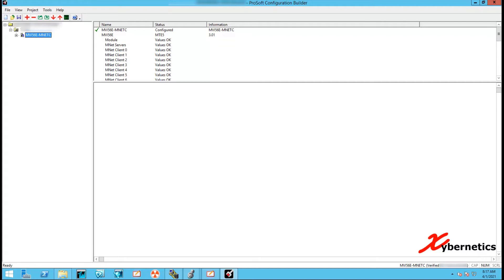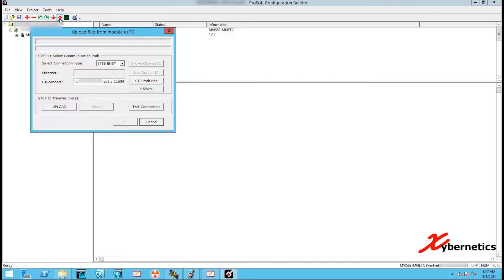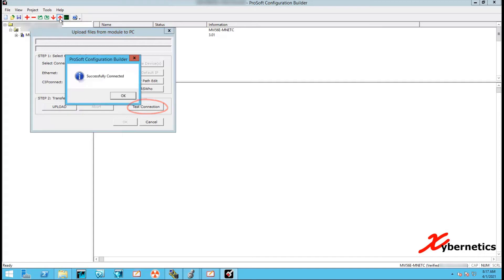The first thing I normally like to do is to read the configuration file from the ProSoft module itself. Click on the red arrow and a pop-up window will appear saying 'upload files from module to your PC.' The first four numbers on the CIP Connect is your IP address of your PLC, not the IP address of the ProSoft module — keep that in mind. Then click the test connection button, and if all connections are good you should get a 'successfully connected' pop-up window.